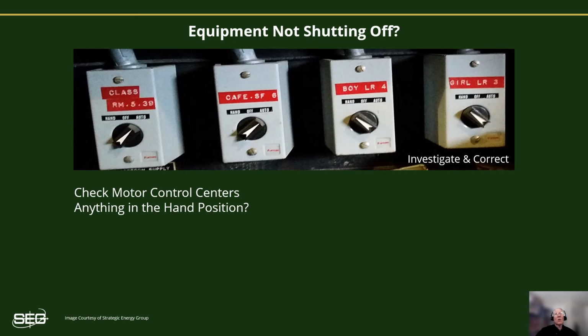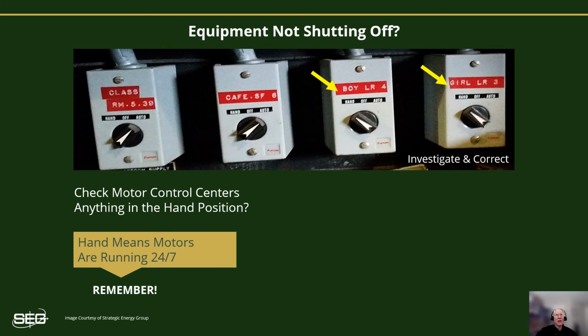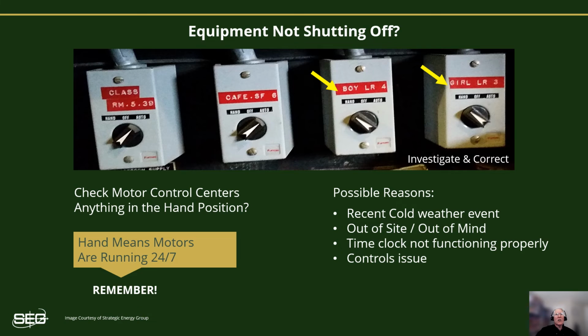Whether during a night walk or even a daytime site visit, always keep an eye out for equipment that's been overridden. It's pretty common to find systems that have been overridden on months earlier due to a brief weather event or maybe some maintenance, but now it's been forgotten. It's also important to review the HVAC systems immediately after a cold or hot weather event to make sure that you catch any overridden equipment that may have been forgotten and is now needlessly running 24/7.